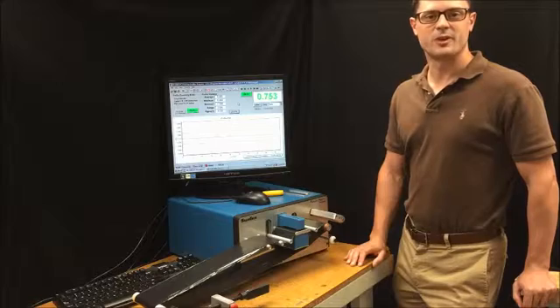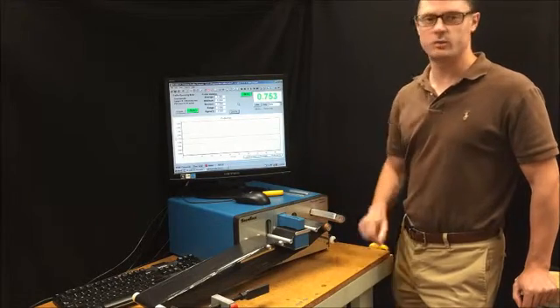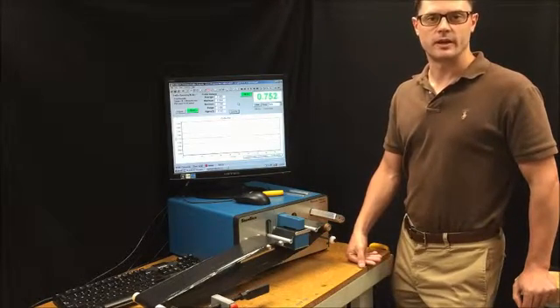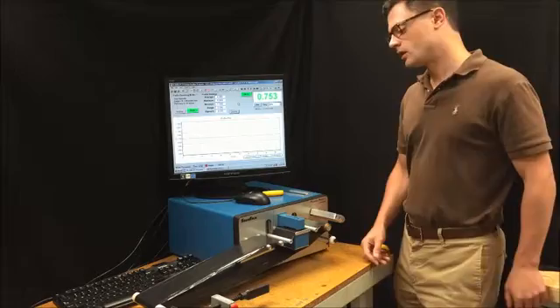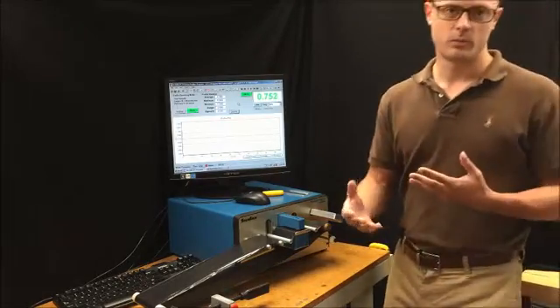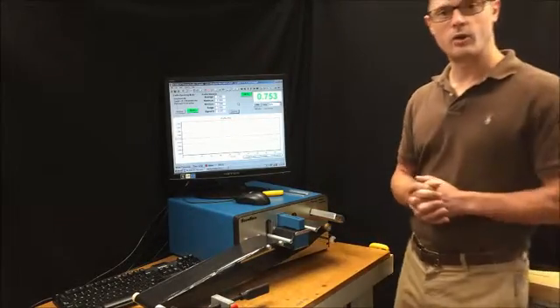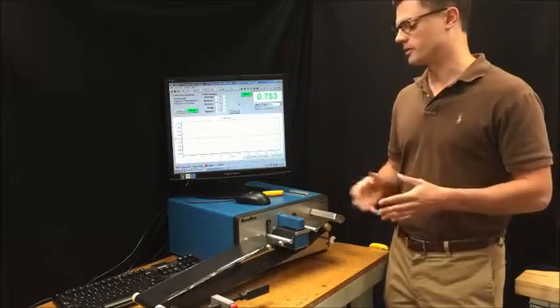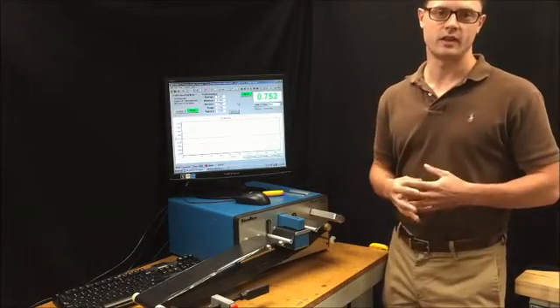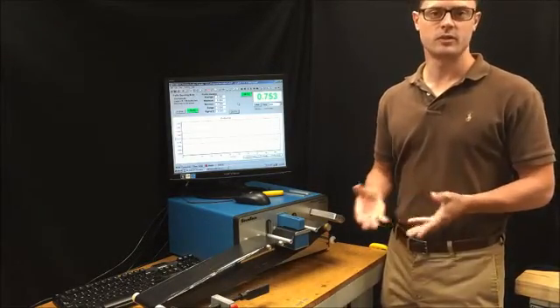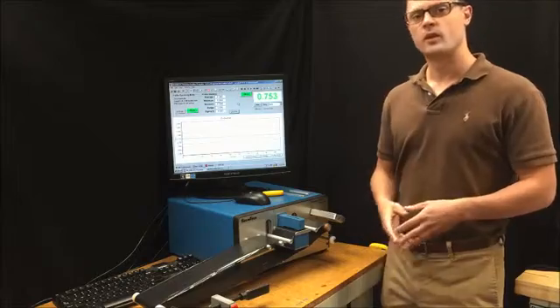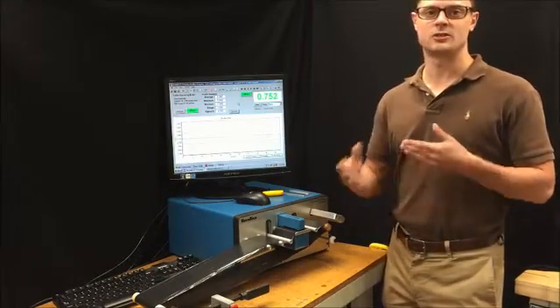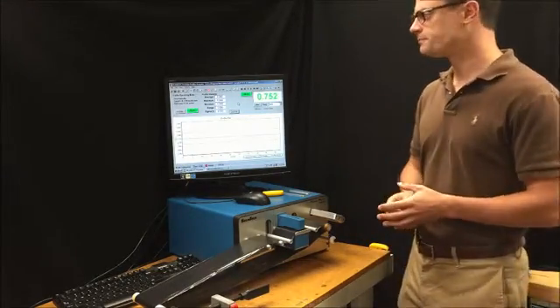Hi, this is Rob Lawrence from SolvTech, and today I'm going to demonstrate the repeatability of the PR2000. The way we represent the repeatability is we repeat two runs and we overlay those runs over the top of each other, and we see how closely they match. If they match closely, then the run is repeatable, and we also want to look at the statistics to make sure their statistics are repeatable as well.